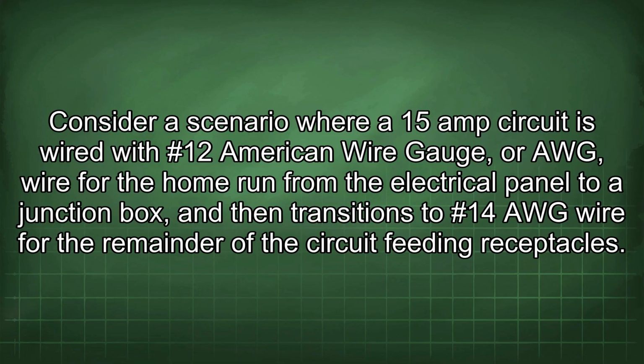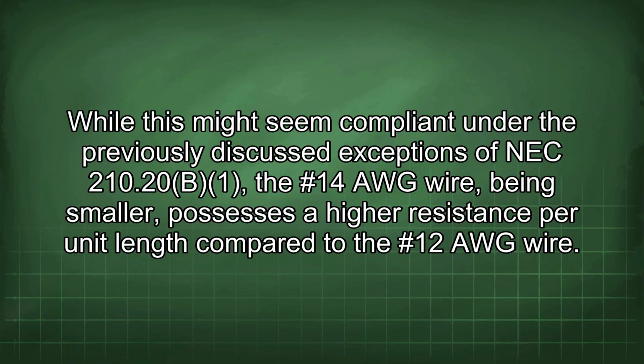Consider a scenario where a 15 amp circuit is wired with #12 American Wire Gauge (AWG) wire for the home run from the electrical panel to a junction box, and then transitions to #14 AWG wire for the remainder of the circuit feeding receptacles. While this might seem compliant under the previously discussed exceptions of NEC 210.20, a #14 AWG wire, being smaller, possesses a higher resistance per unit length compared to the #12 AWG wire.